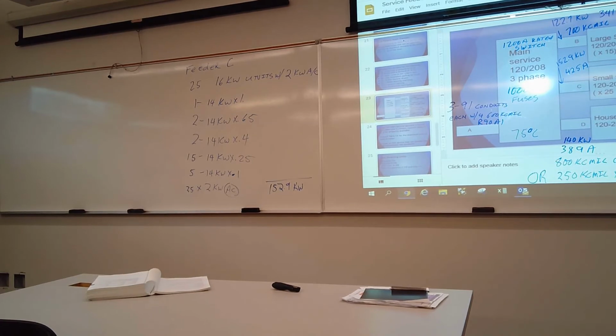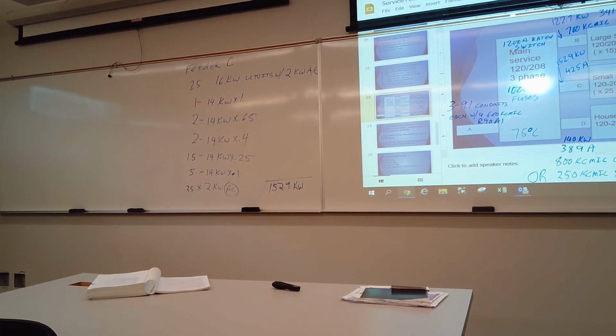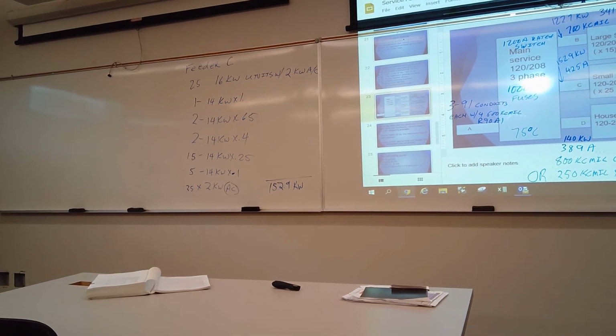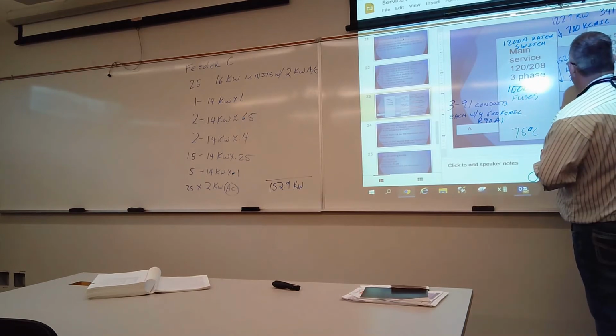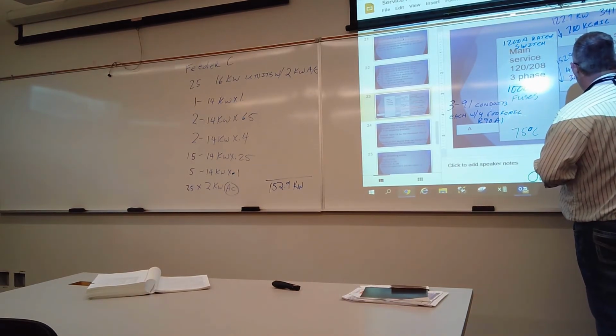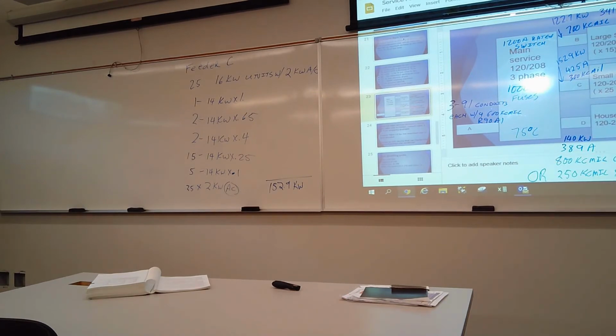So we're probably going to be splitting that in half and running parallels, right? So for 213 amps, we have to go up to 300s. 300 kcmil times 2 parallels. We're going to have 2 conduits with 4 conductors in each here, depending on how we do it: 1 conduit with 4 800 kcmils, or 2 conduits each with 4 250 kcmils at this location.